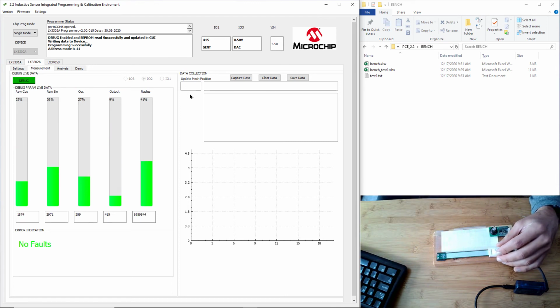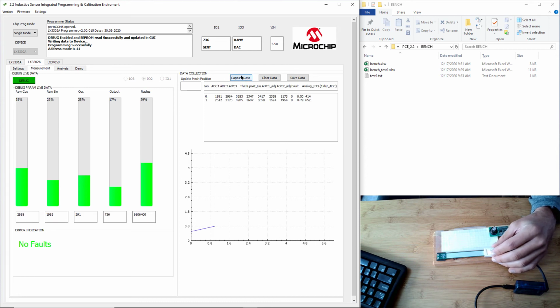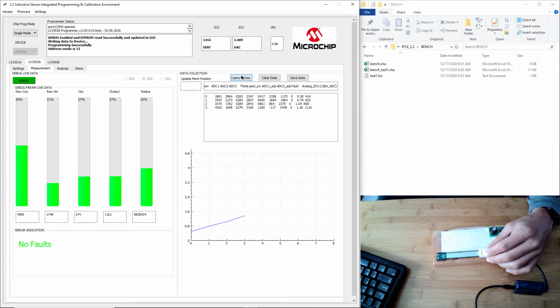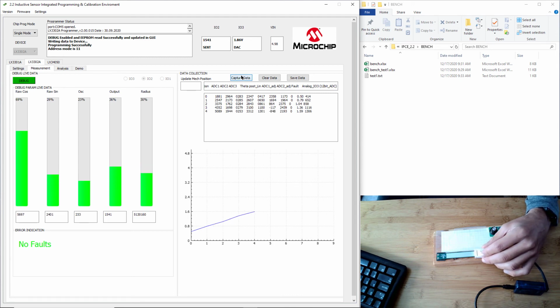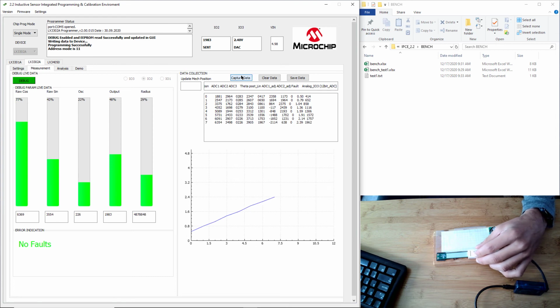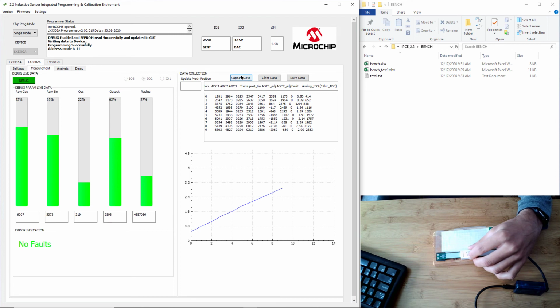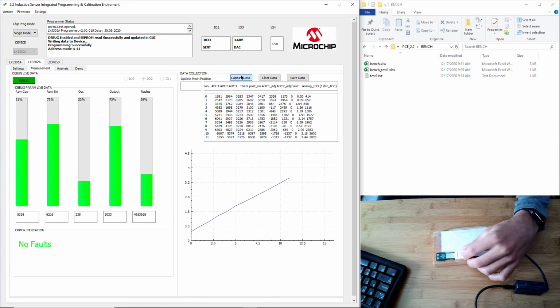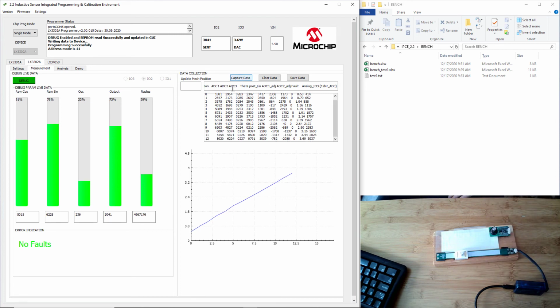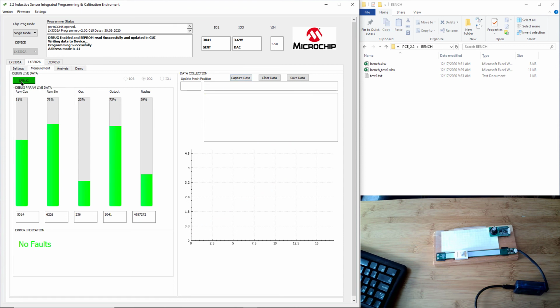And I'm going to go to the start page and just check to ensure that the inflection point has disappeared. And you can see right in the middle, it no longer is there because that origin parameter got corrected. Now, one other thing you'll notice is that we're still in the debug mode. So you do need to click that again, and it takes us out of the debug mode.